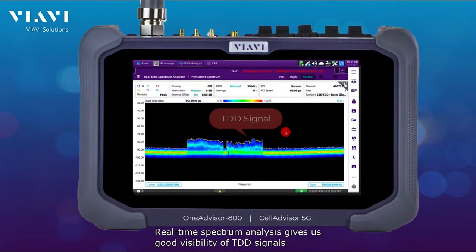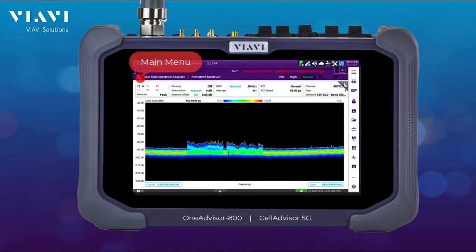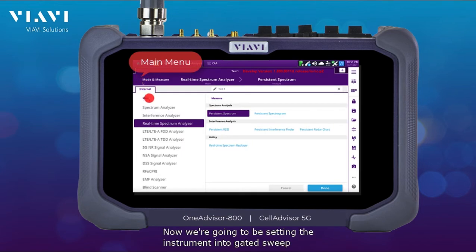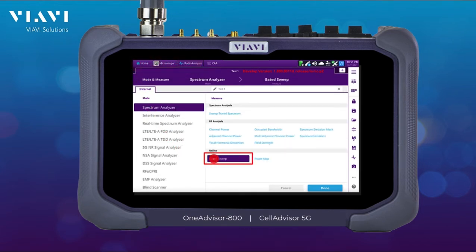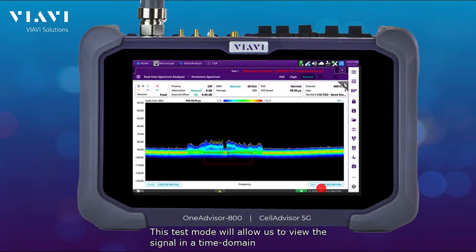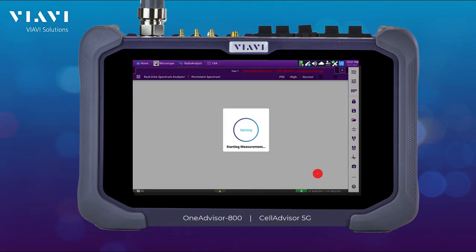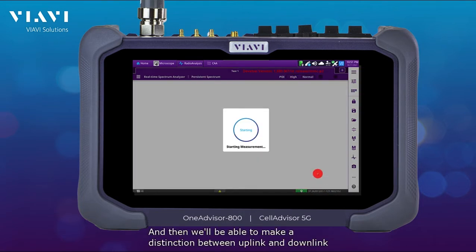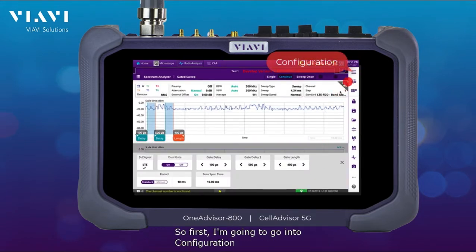Real-time spectrum analysis gives us good visibility of TDD signals. Now we're going to be setting the instrument into GatedSweep mode. This test mode will allow us to view the signal in the time domain, and then we're going to be able to make a distinction between uplink and downlink.